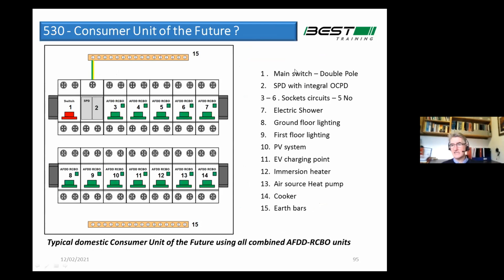Now, next big change, and I'll dwell on this one because it's creating lots of queries, and some gentleman sent in a query yesterday, and I unfortunately couldn't commit myself to answering all of his queries, but I'll address some of them now. First thing about consumer units, in part 42, which deals with spread of fire, they said that a consumer unit should be manufactured from metal, non-combustible material, or materials complying with a particular EN reference, which I can't remember off the top of my head, EN 60670-24, I think it is. Basically, it's a standard that deals with flammability tests, glow wire tests for products.